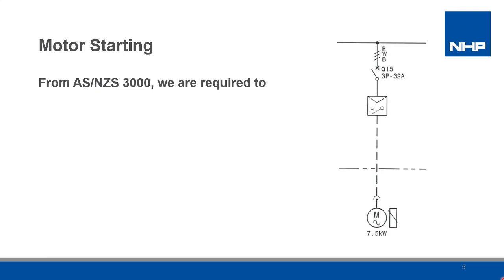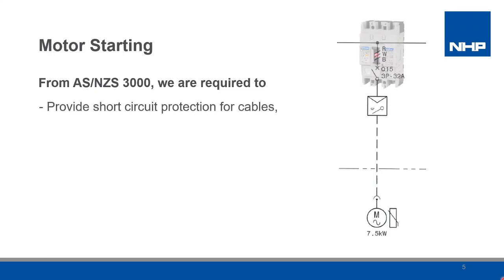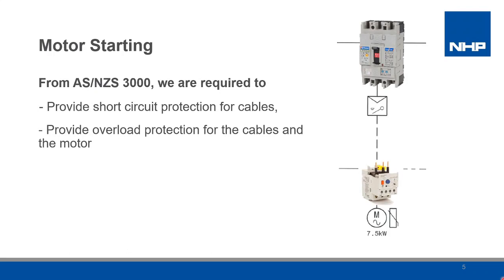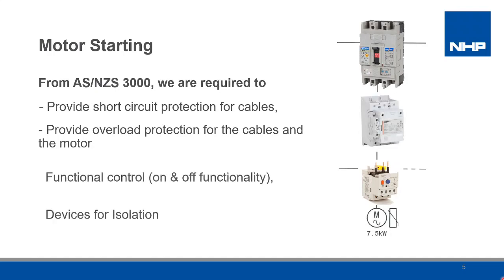For a typical DOL starter, the minimum requirements of a motor starter are from AS/NZS 3000. Short circuit protection is required, and the most common device now used is a circuit breaker, but fuses may also be an option. Motors are required to have overload and over temperature protection, and normally use an overload relay, which also provides overload protection for the cables. The contactor gives us functional control for starting and stopping the motor, and is normally selected based on AC3 duty. These are the three components normally associated with a DOL motor starter circuit.